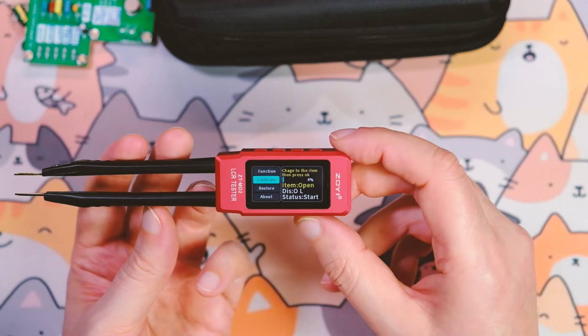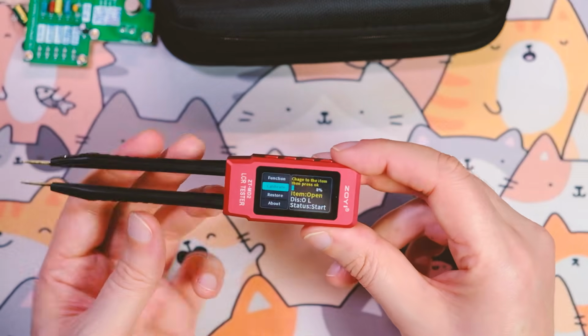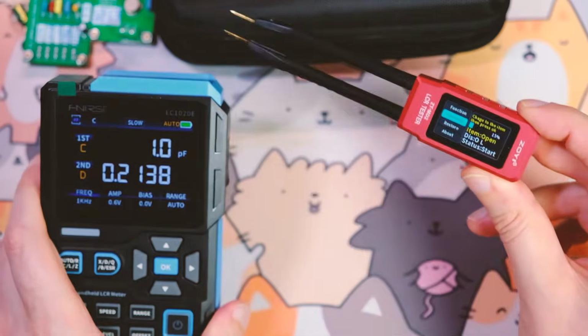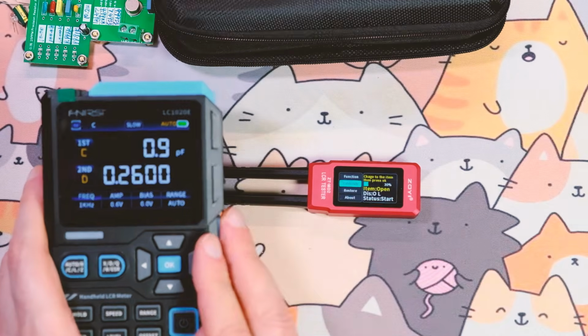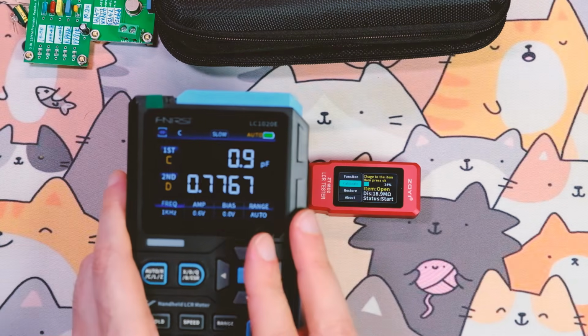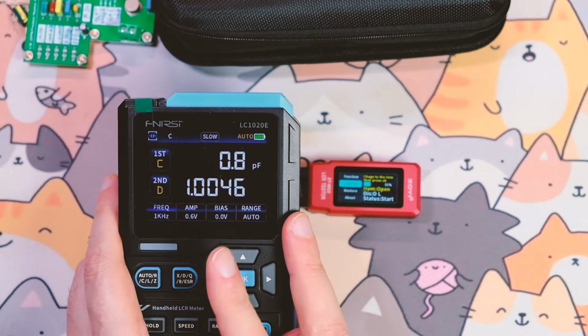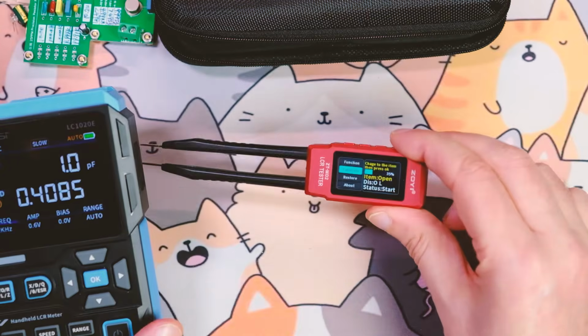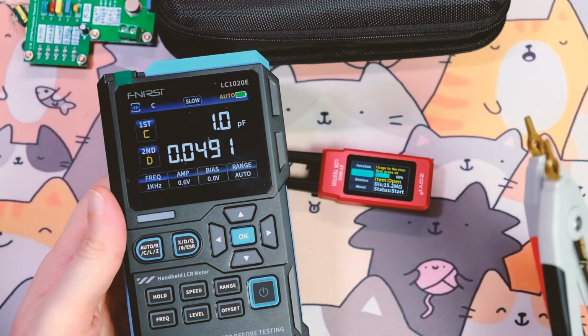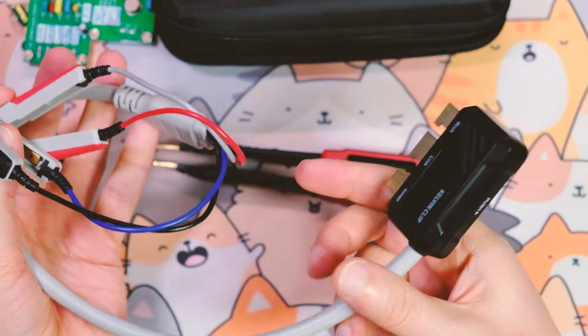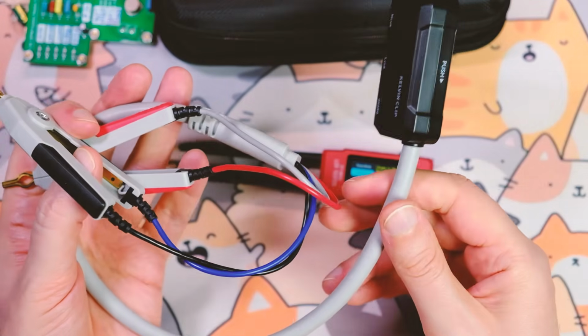While the calibration is running, I'll show you this device. This is the LC1020E. It shows 5 digits. It has better resolution and measures some parameters more accurately. The ZOYI has 4 digits. The LC1020E uses a cable with Kelvin clips. The cable itself is shielded and quite long, about 40 centimeters.